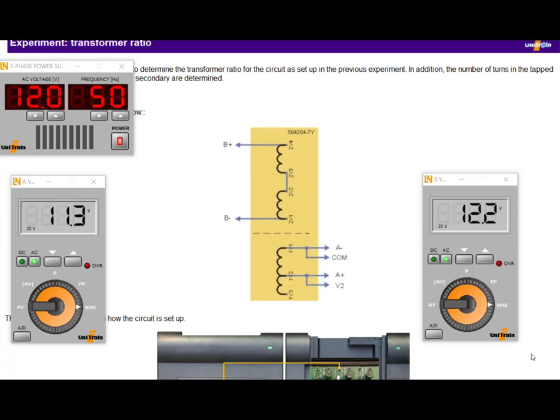Next experiment is the transformer ratio. We use the formula V2 over V1, the voltage of secondary divided by voltage of primary, equals N2 over N1. We apply voltage to two windings, and assuming we know the number of turns for one winding, we can use the formula to find the number of turns for the other winding. First, we apply voltage to the winding between 1V2 and 1V1.